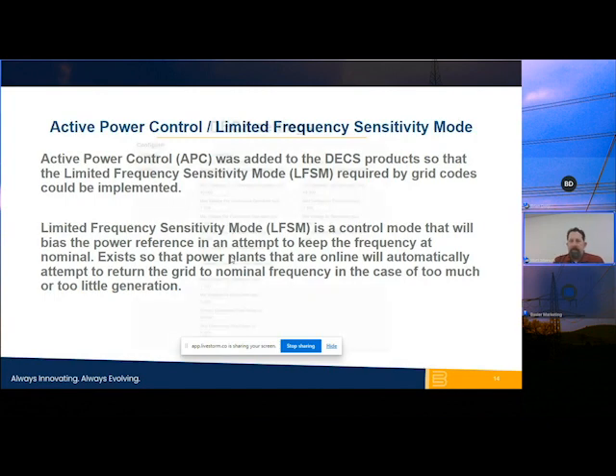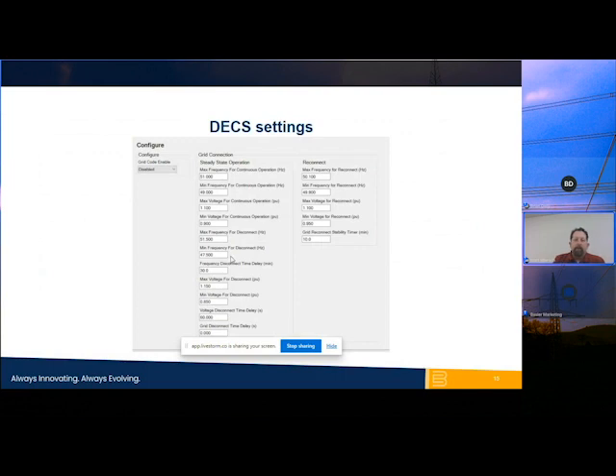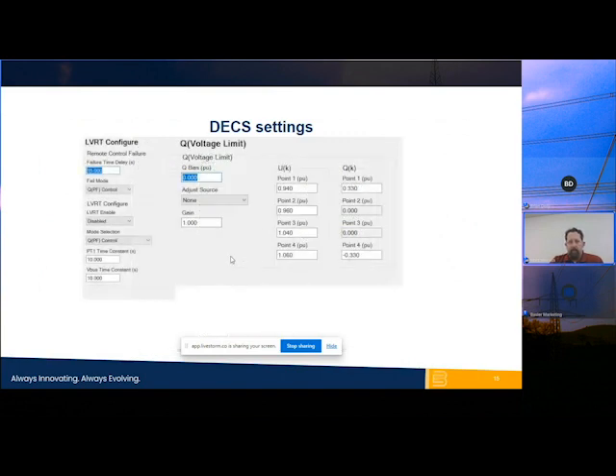I just have a few settings of how all these things are implemented. This is again a screenshot from the DECS 250. We would go into the DECS 250 and put our settings in there. It's going to tell us our grid connections. Again, this is one we already looked at, but it's basically our grid connections and when we're going to connect or disconnect. Then we can look at our low voltage and frequency ride through time delays, and what modes of operation we're going to operate in under those conditions. This is all in the configuration screen. And then our voltage limit modes of operation.